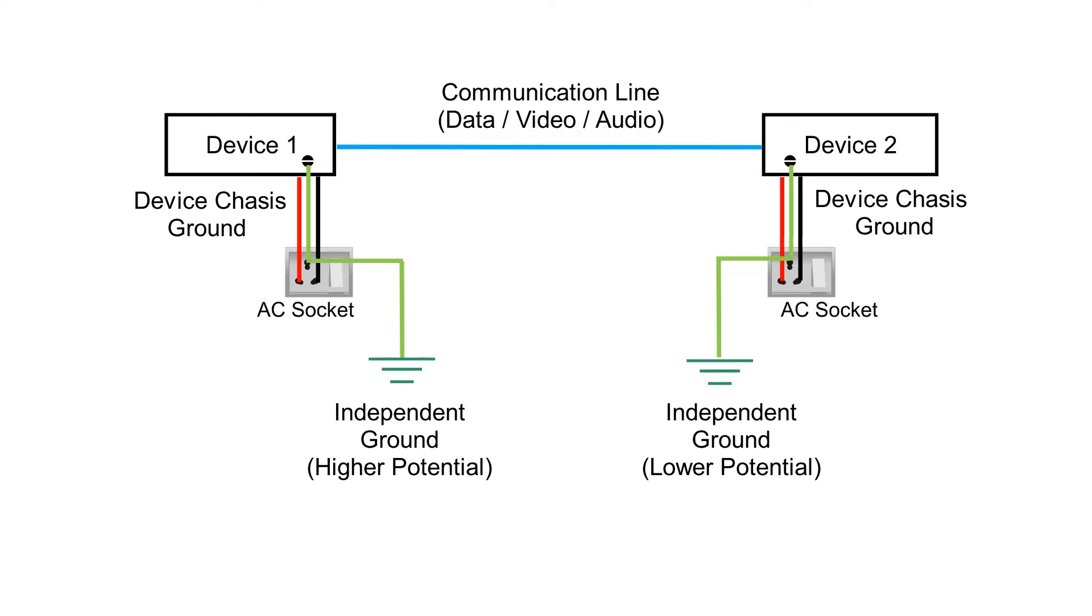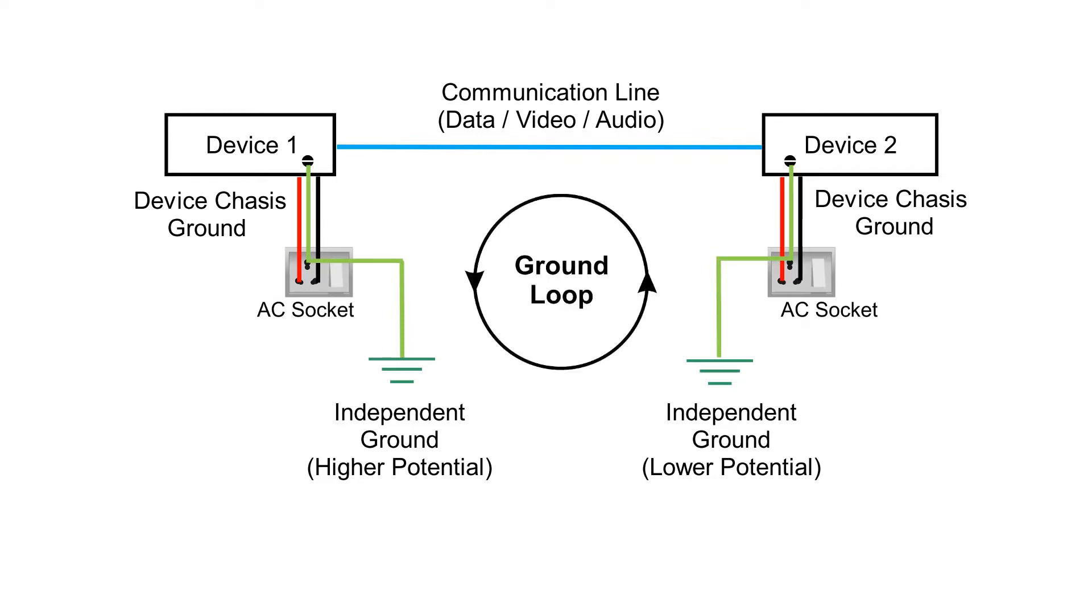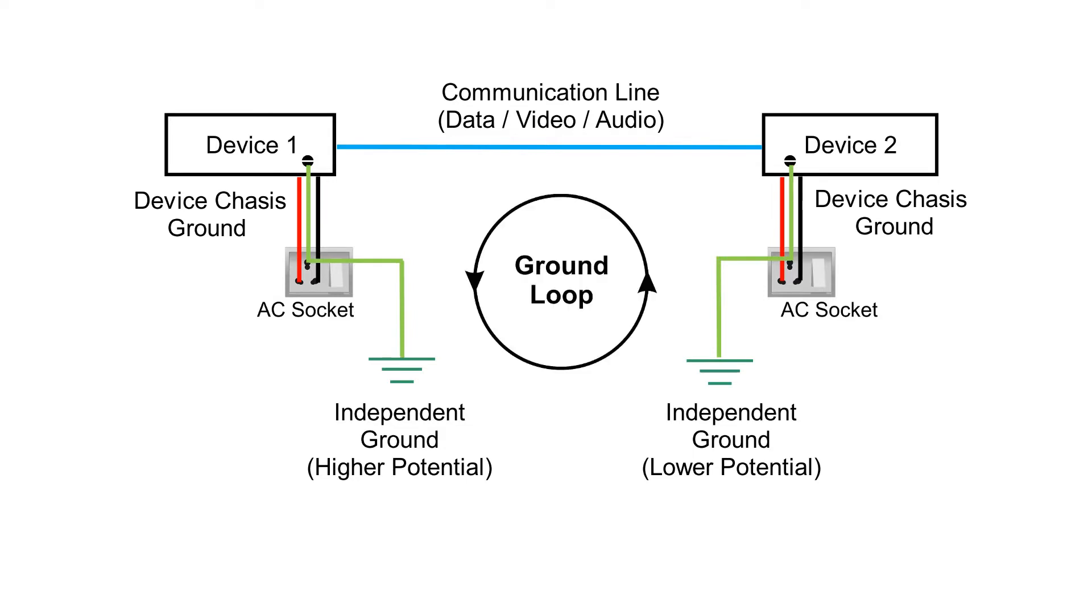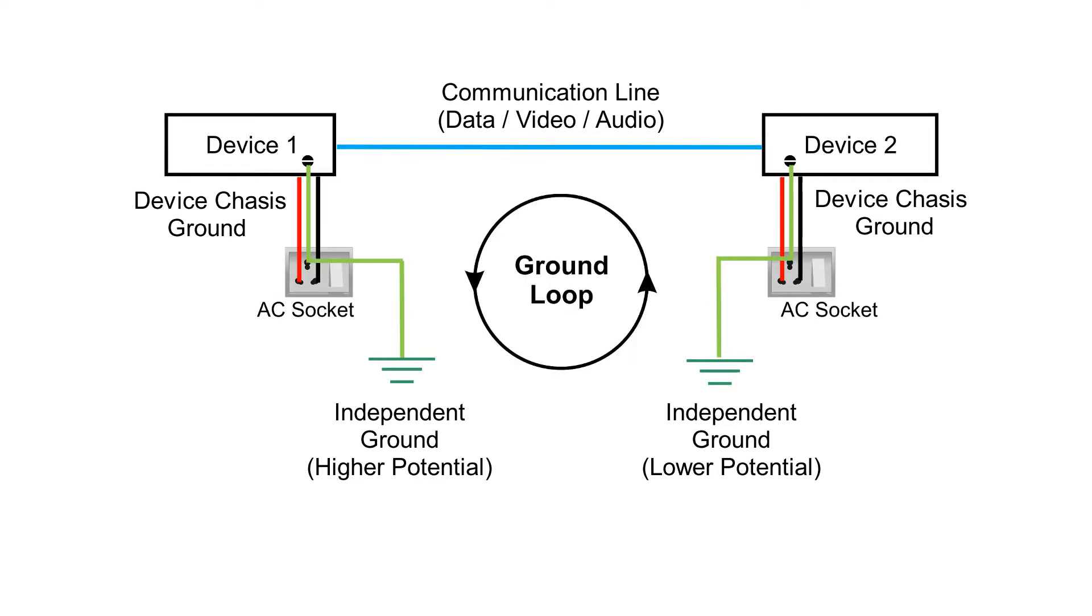Ideally, all grounded points of an electrical system should be at the same potential. However, different points of the same grounding system even within a building may have different potentials leading to the flow of current from higher reference ground point to a lower one through a circular path that uses the data line.